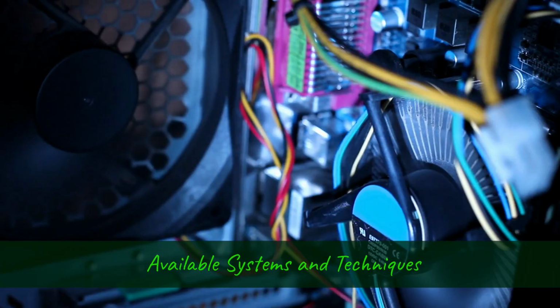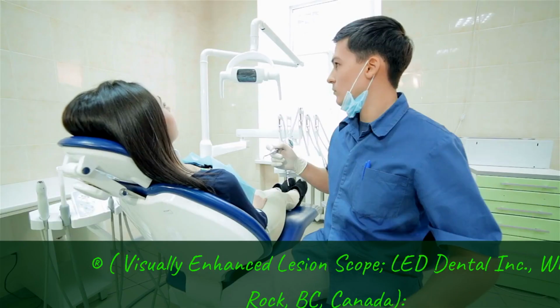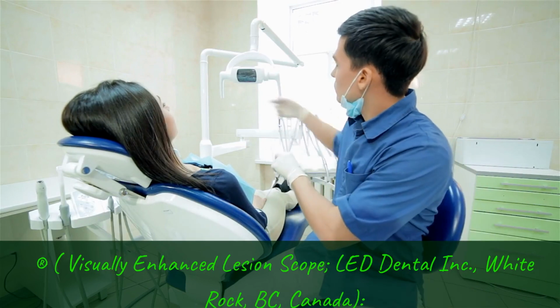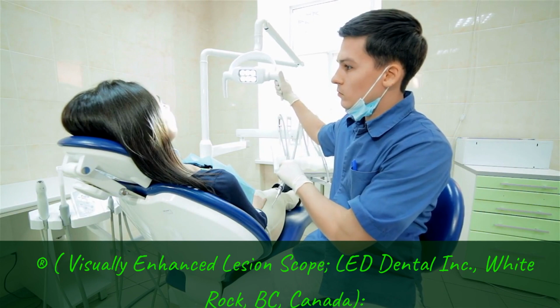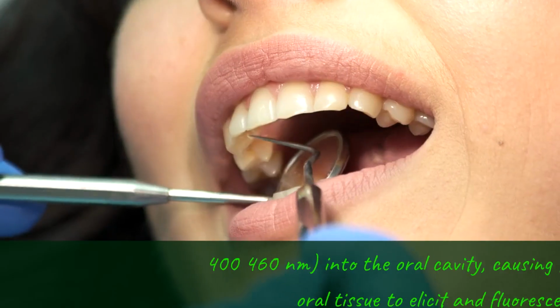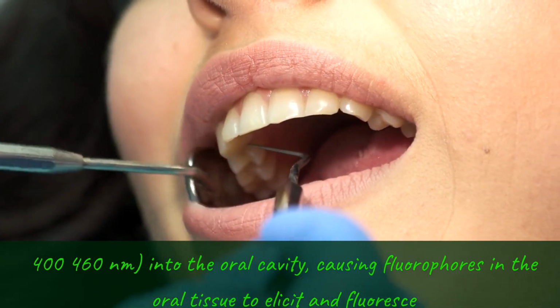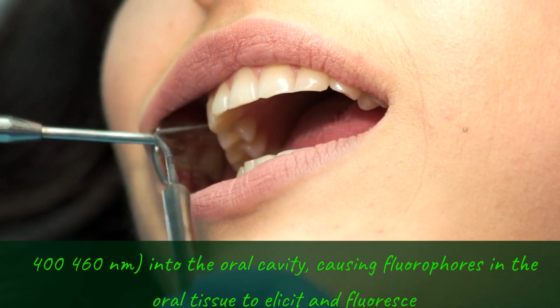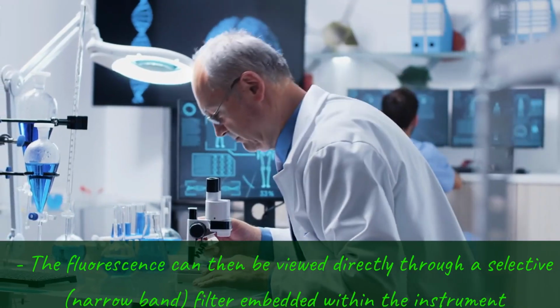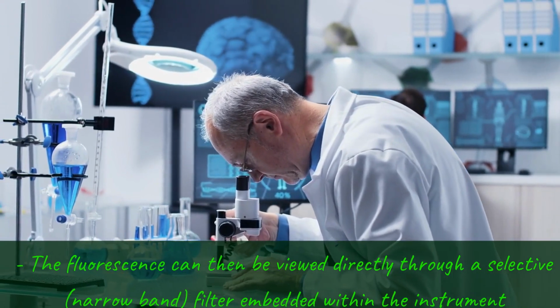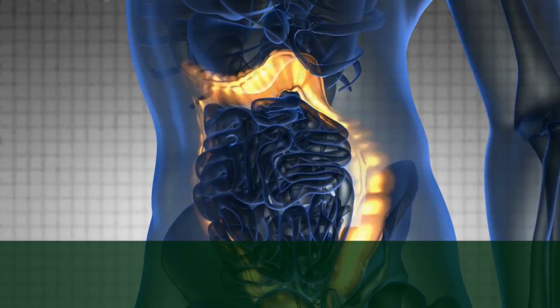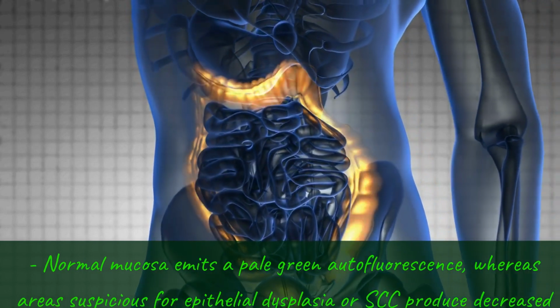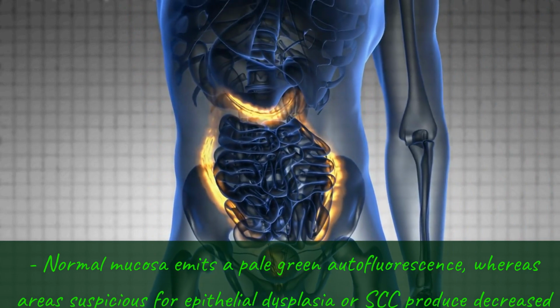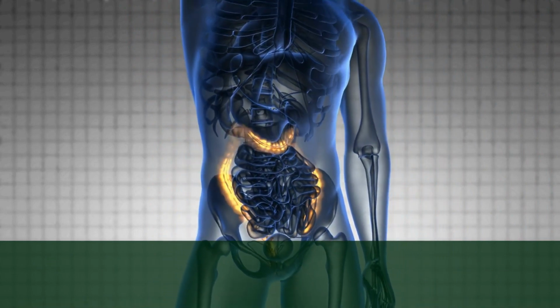Available systems and techniques. The VELscope, Visually Enhanced Lesion Scope, LED Dental Incorporated, White Rock, British Columbia, Canada. The device works by emitting a cone of light in the blue spectrum, 400 to 460 nanometers, into the oral cavity, causing fluorophores in the oral tissue to fluoresce. The fluorescence can then be viewed directly through a selective, narrow band filter embedded within the instrument. Normal mucosa emits a pale green autofluorescence, whereas areas suspicious for epithelial dysplasia or SCC produce decreased levels of autofluorescence and appear darker compared to the surrounding healthy tissue.